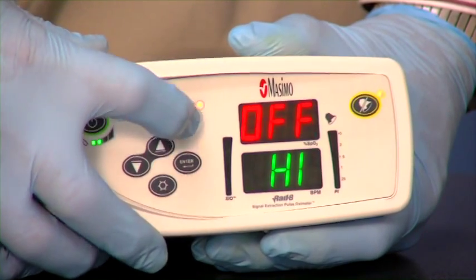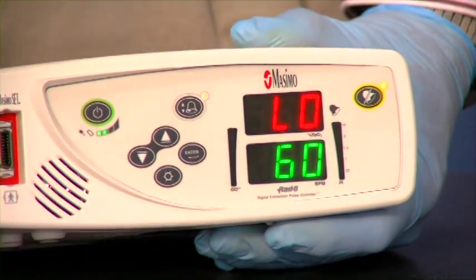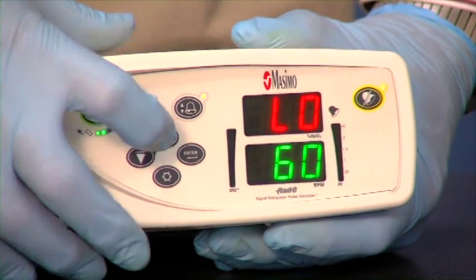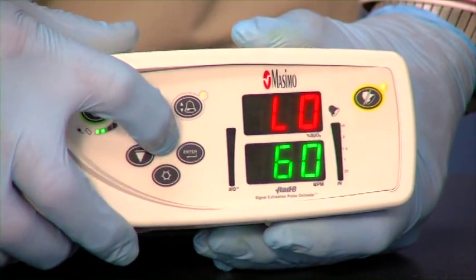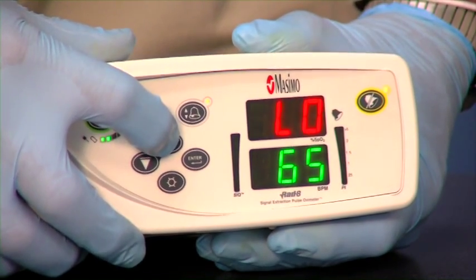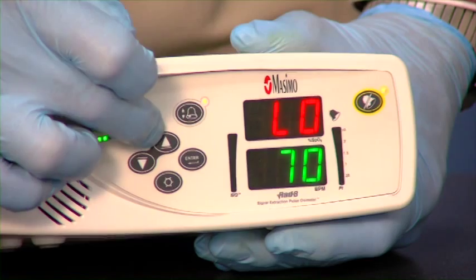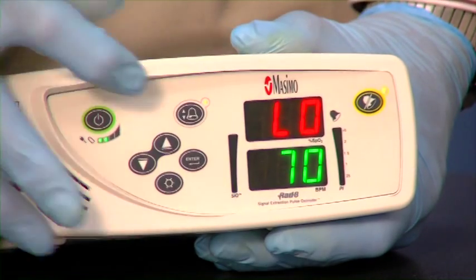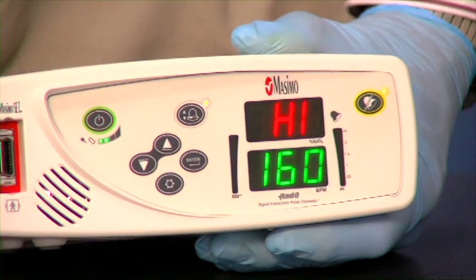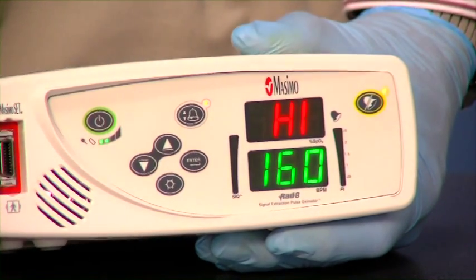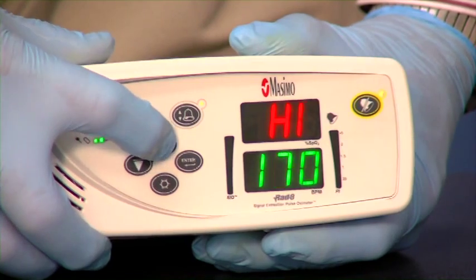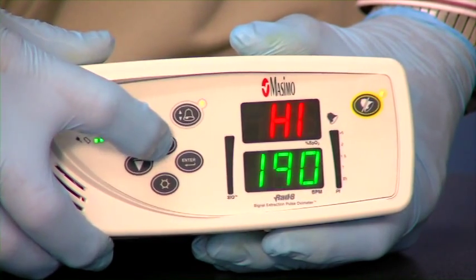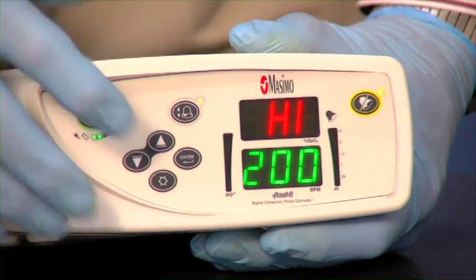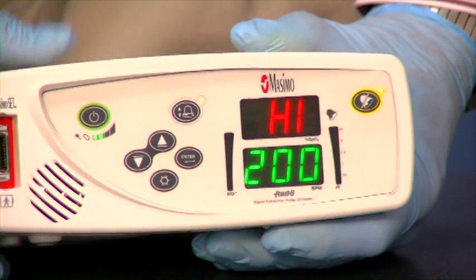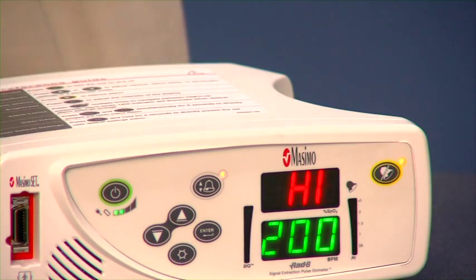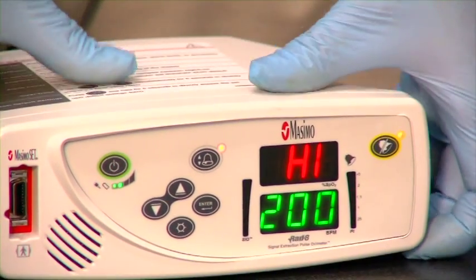When we press that button a third time, it's going to take us to our low heart rate. Okay, so if we want our pulse rate to be at 70, which is what our default is on the low, we use the increase button or the decrease to take it to 70. When we press the selector button a fourth time, this is how we adjust our high heart rate setting. So we're going to increase that up to 200. You see it goes up in increments of 5. Now we can enter it in, or we can simply leave it alone for a few seconds and it will return to the main screen.